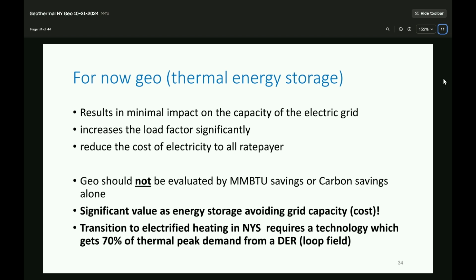So we shouldn't look at how much total million BTUs we can save. We've got to look at what it avoids in grid capacity, because this is really where the value is. Keep in mind, we can shave that monster peak by 70% and more.